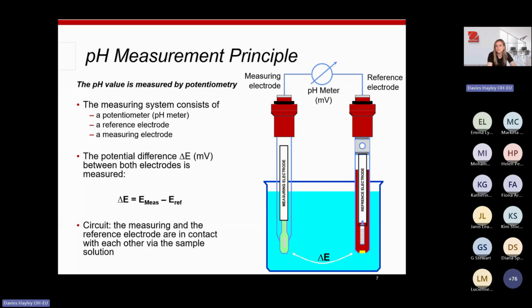So the measurement principle is pretty simple if we dial it back a little bit. The pH value is measured by potentiometry. So think of a pH meter like a specialized voltmeter. The voltmeter or the pH meter is in the middle, and then you've got your reference electrode, and you've also got a measuring electrode as well. The measuring and the reference electrode are in the solution and they are in contact with each other via the sample solution, and that completes the circuit of the voltmeter. And then the difference between the two electrodes is measured, and that will give you your pH reading.